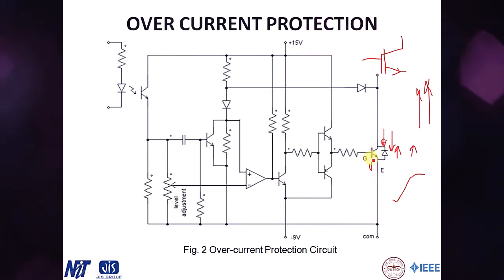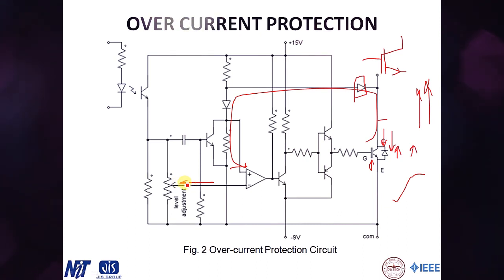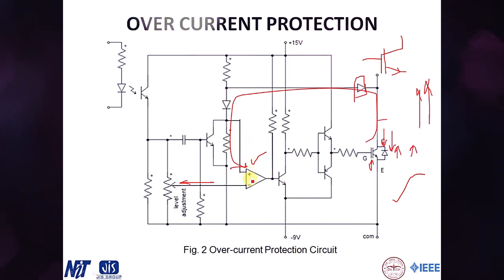We use this rising voltage drop to protect the IGBT. A feedback diode senses the collector-emitter voltage drop and feeds it back to a comparator. The comparator compares this feedback voltage against a reference voltage representing the normal operating voltage drop. During a fault, the feedback voltage increases beyond the reference, so the plus terminal voltage rises and the comparator outputs a high signal.